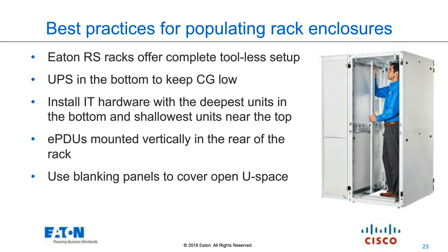When it comes time to start stacking equipment, put the UPS in the bottom, particularly if you're looking in the 5 to 11 kVA range. Those systems tend to be heavy, and keeping the UPS at the bottom of the rack keeps the center of gravity as low as possible.